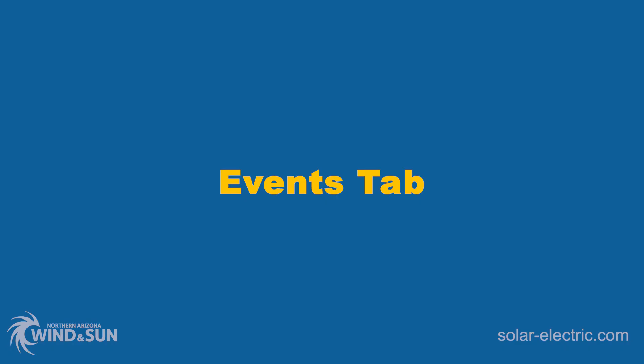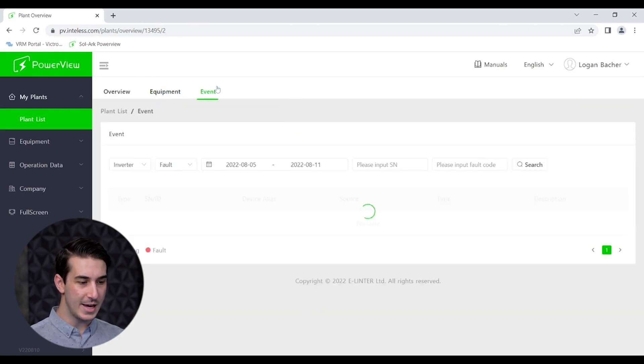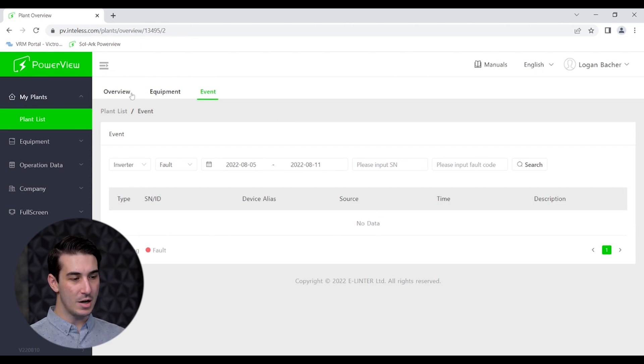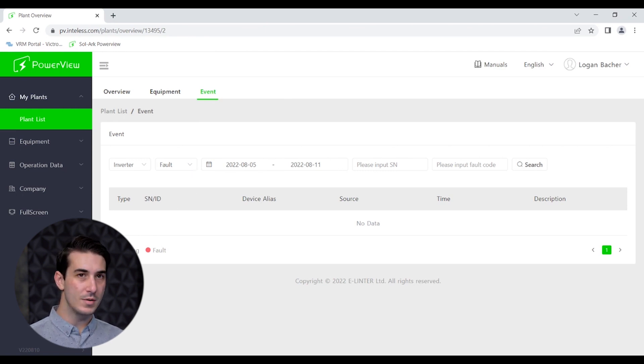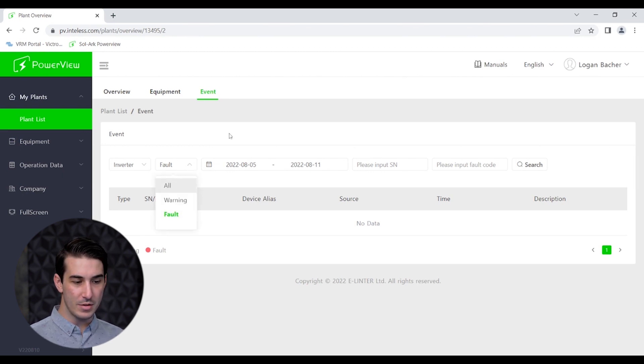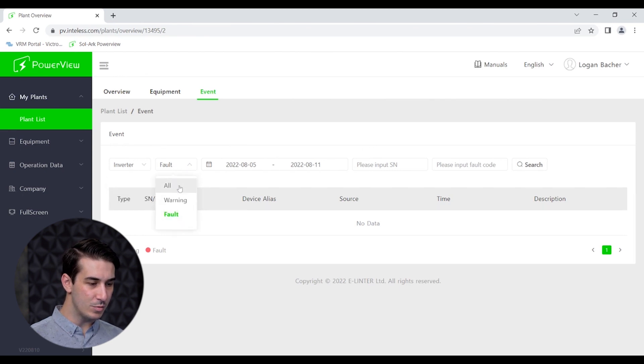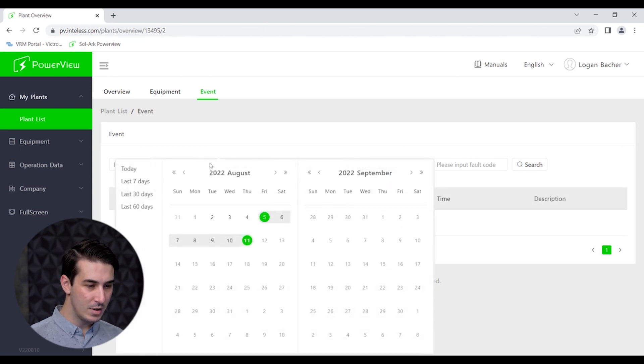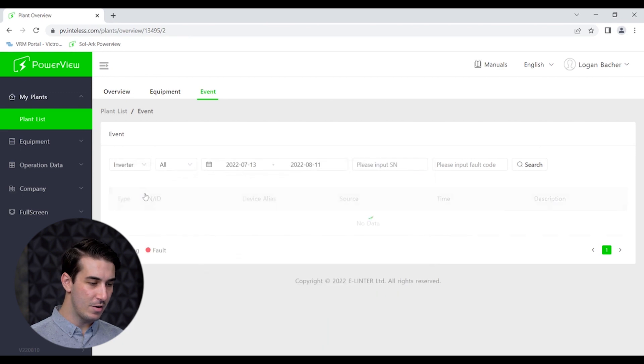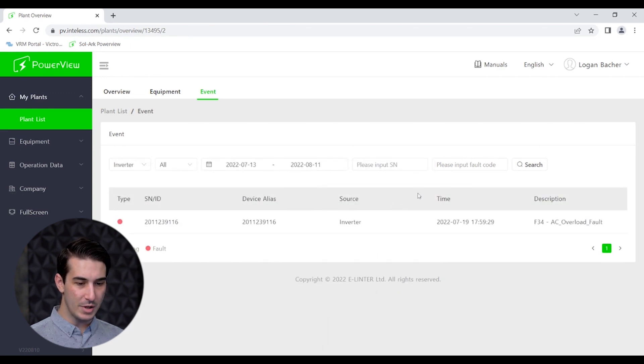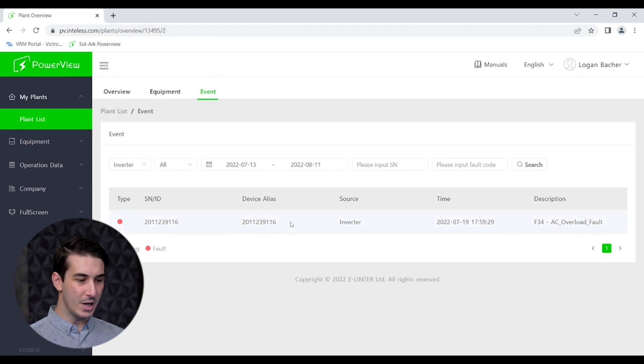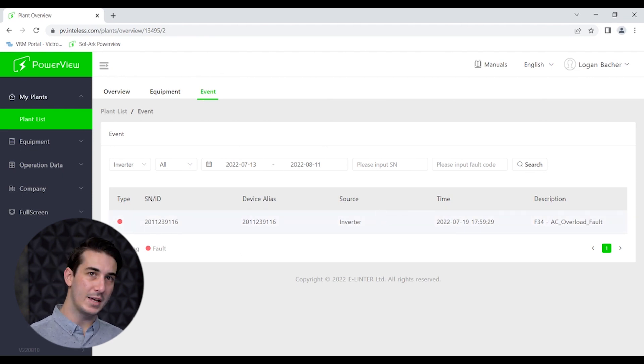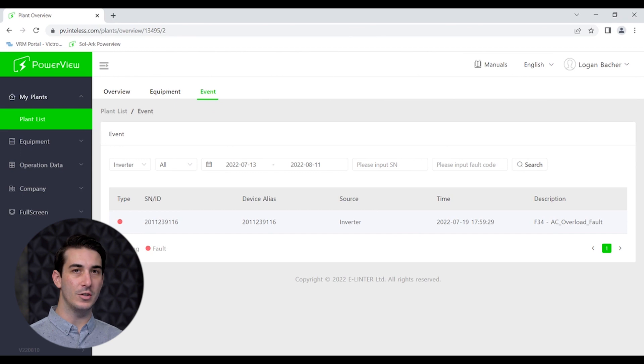Now that we've walked through the equipment section in PowerView, the last thing to show you here on the site is the event tab. That's up top right next to overview and equipment. You can click event and this is going to show you what faults or events or warnings the inverter has logged over time. In this case there's nothing really to see at the moment but you can play around with these. We'll look at all both warnings and faults and you can select the date range manually or using one of the already populated ranges over to the left there. We'll click on last 30 days for example and in this case it did register a fault back in July, an AC overload fault. This page under event is really just allowing you to look back at previous warnings or faults, seeing what happened and when exactly that event occurred in your system.